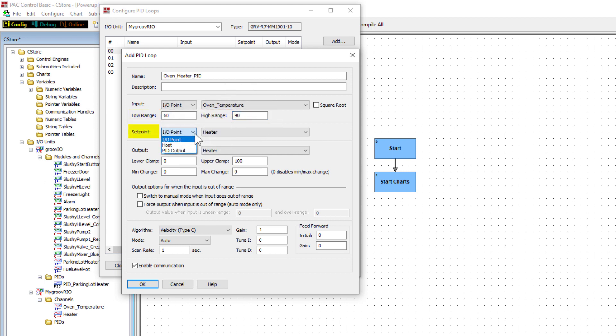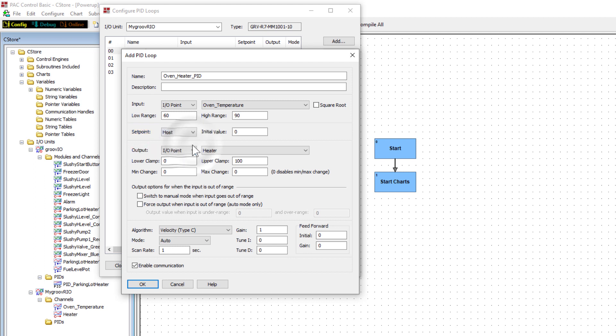Next is the set point. The set point can come in from an analog point, from host if it's going to be controlled from PAC control, PAC display, a PID, or a point from another I.O. unit, or be set by the output from a cascaded PID. I'll choose host. Notice what the default value is set to, zero. Caution here, you want to be sure you enter an initial set point value here. Otherwise, until you initialize the set point, such as through a command in your strategy, then zero is your set point. If that's not your set point, you might get some unexpected fluctuations in your process. Enter an initial value of 84 degrees.